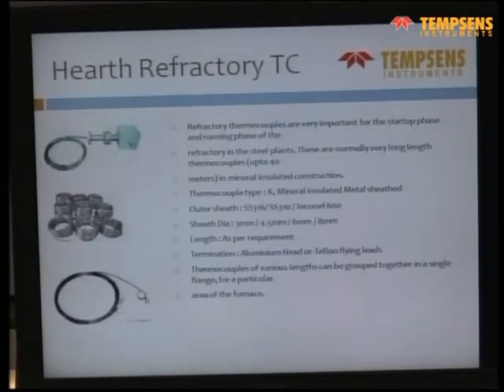Yes, sir. For the first one, it's a multi-point. It's like many MI thermocouples placed together. One can be 5 meters, another 7 meters, 8 meters. They are all put together in one junction box as the connecting box. But those are similar to MI thermocouple? All are MI thermocouple. We have a possibility.